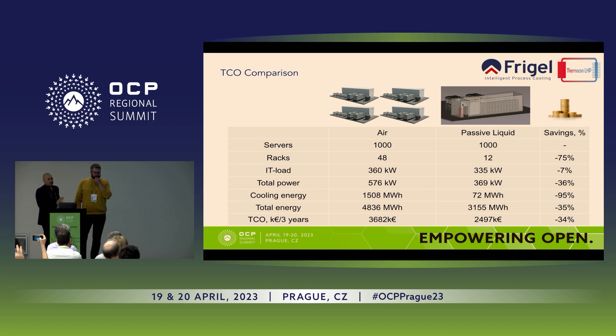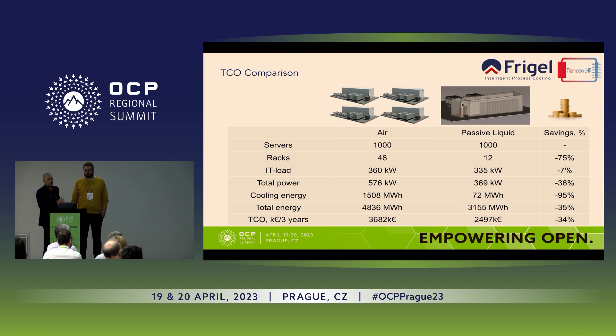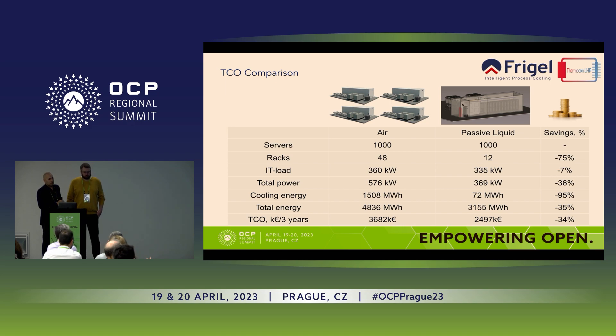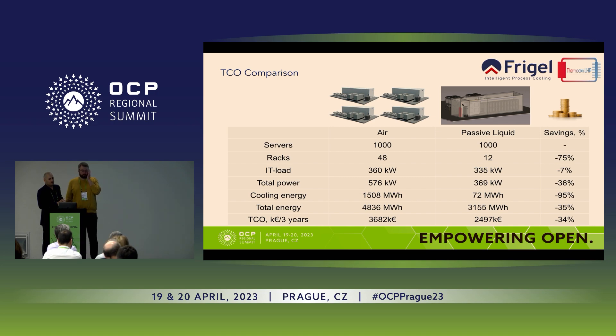Now we can make a comparison: 1,000 servers air-cooled versus 1,000 servers liquid-cooled. In the first case, we need four modular data centers; in the second case with liquid cooling, we need just one. So fewer racks, less IT load because less fan work is needed. Total power is reduced by 36%, requiring less UPS, fewer gensets, fewer transformers, and less energy equipment. Cooling energy is reduced by 95%, and overall total energy is reduced by 35%. Over three years, CAPEX is cheaper, OPEX is cheaper, and we save 1.2 million euros on 1,000 servers.